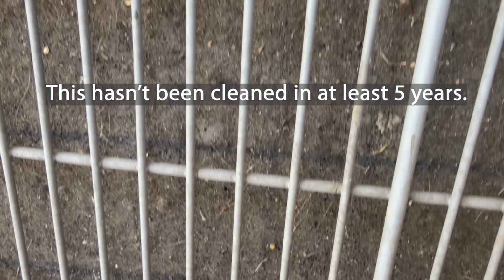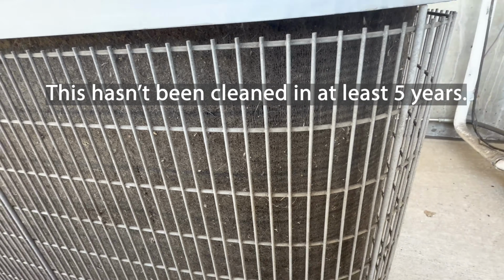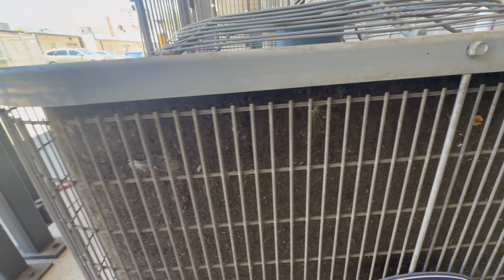How much do dirty condenser coils affect how your HVAC system works? And is it worth having them cleaned professionally? Here's a look at a condensing coil that's pretty plugged all the way around. And I would think that this would definitely affect how efficient the system is. As you can see, there's not many open fins. There's a little bit of a space right there, but I would say probably 80% of this one is covered.